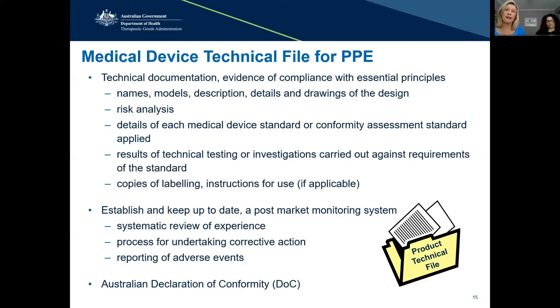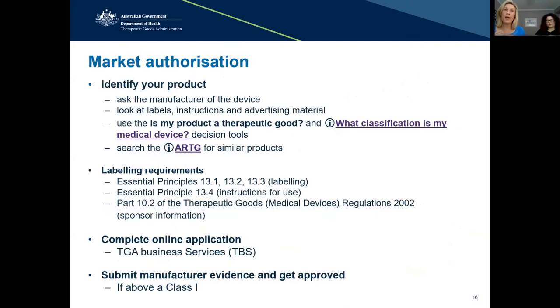For class one non-sterile devices, the manufacturer goes through the list of essential principles and is satisfied they've met those requirements. They then do a self-assessment process and make an Australian declaration that all of those requirements have been met. That's the point when the manufacturer, and if they are also acting as the sponsor in Australia, or if they're assigning that responsibility to somebody else, applies for market authorisation.